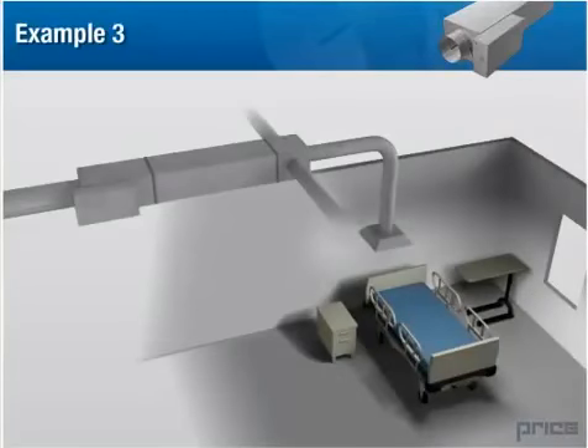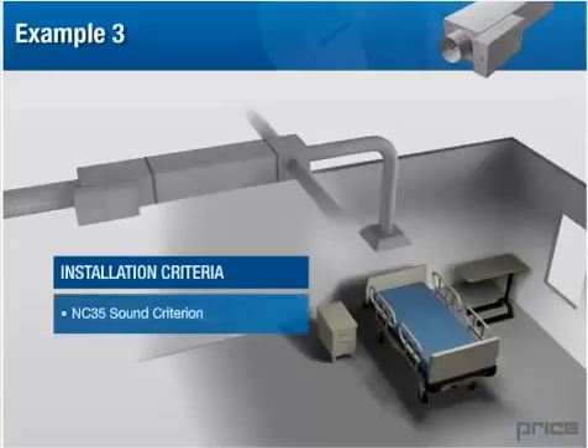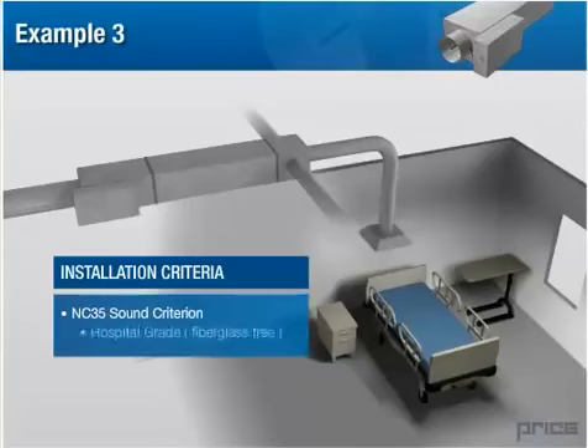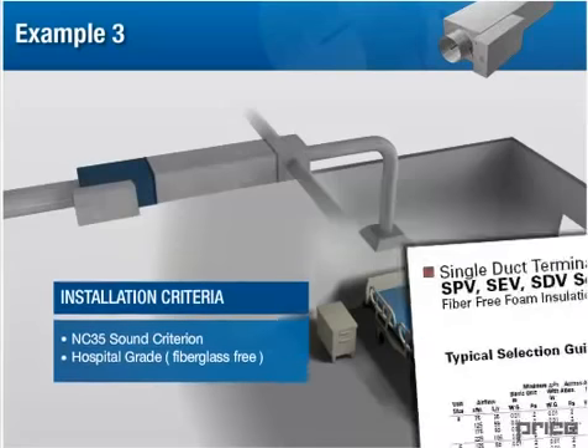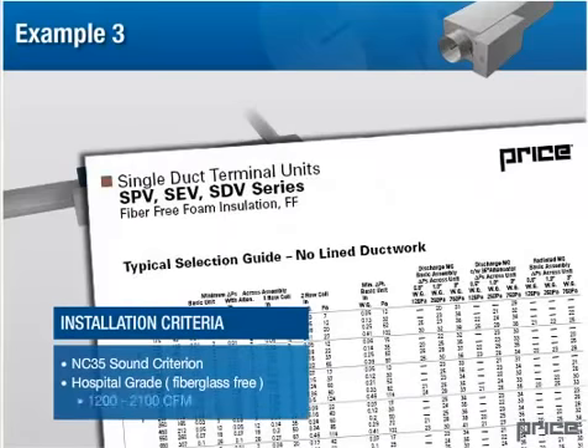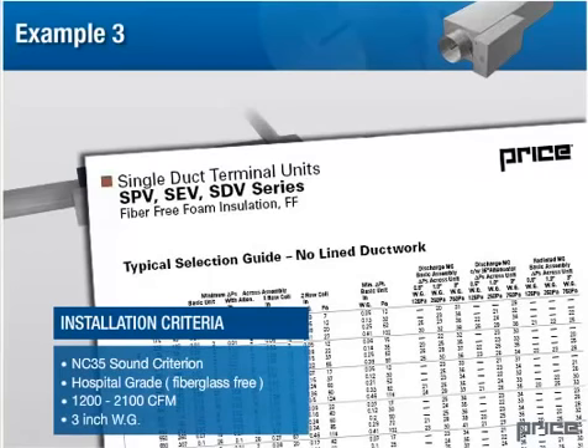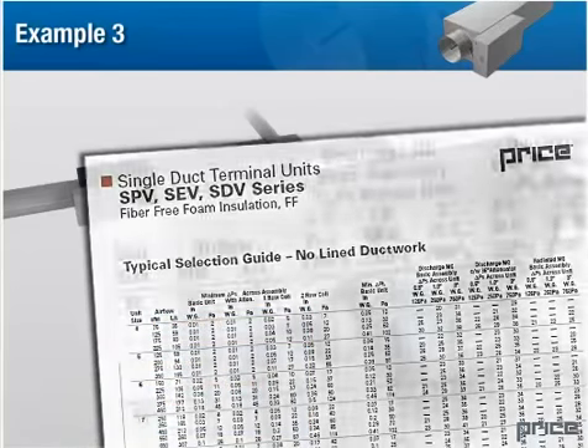Example 3. Now let's take a look at another situation, this time for a patient room in a hospital, where there is an NC 35 sound criterion. In this case, we have the same requirements as before, with the added requirement of hospital-grade or fiberglass-free insulation. Typically, we now have to select a configuration that will not introduce fiberglass fibers in the airstream. We will have to eliminate any lined ductwork, and we may choose to go with a fiber-free foam liner in the terminal unit. Although the NC rating for a standard 12-inch SDV at 1200 to 2100 CFM and 3 inches of static pressure meets our noise requirements, our new fiber-free configuration is significantly louder.